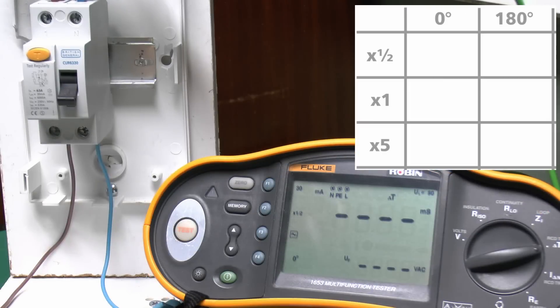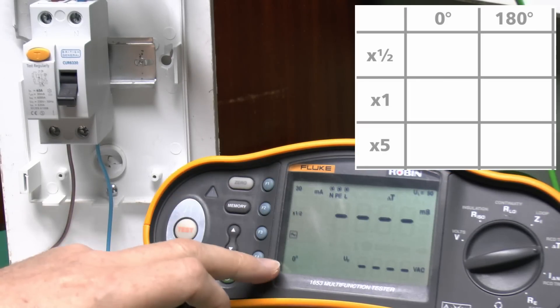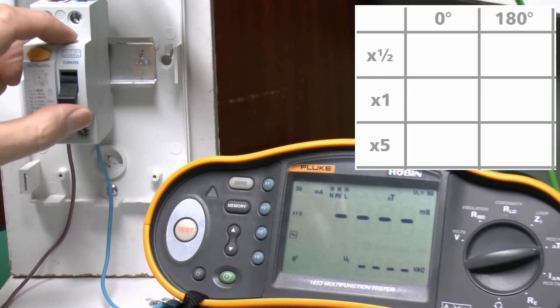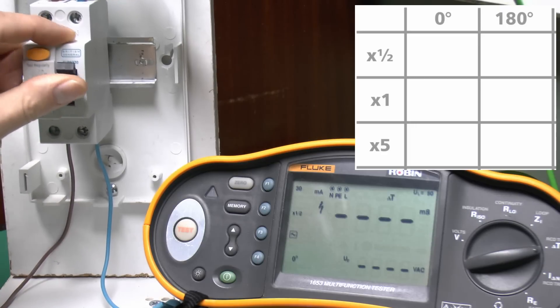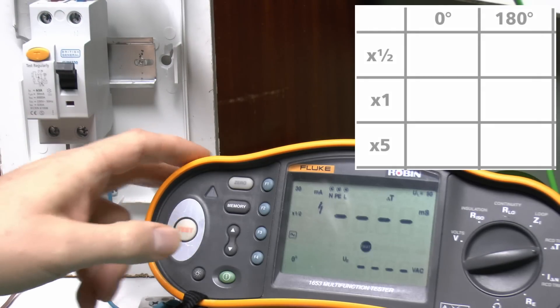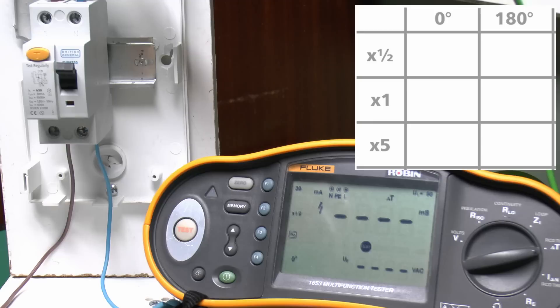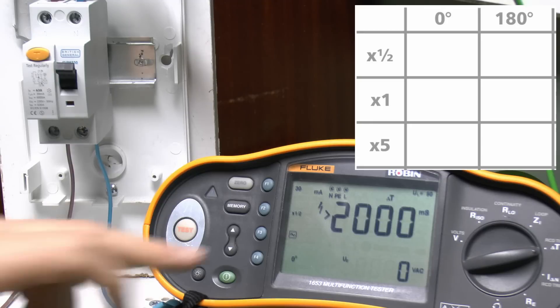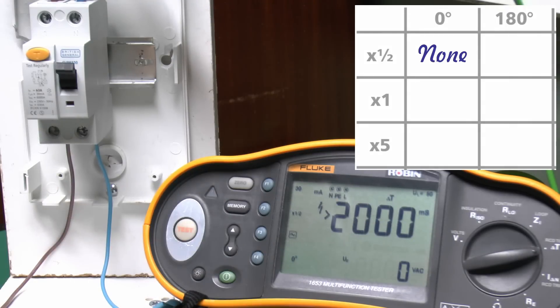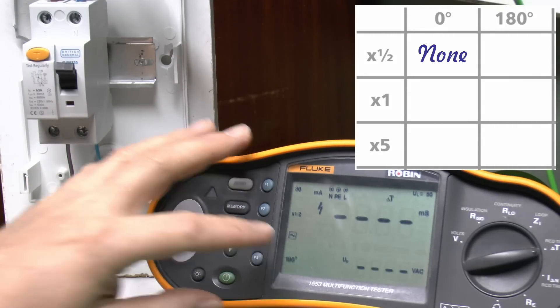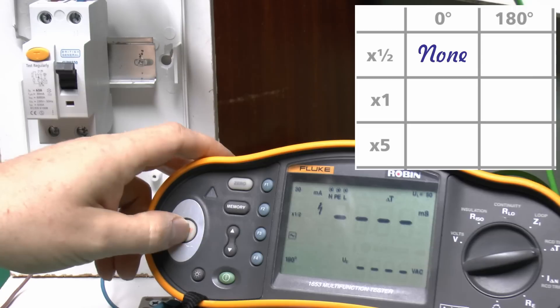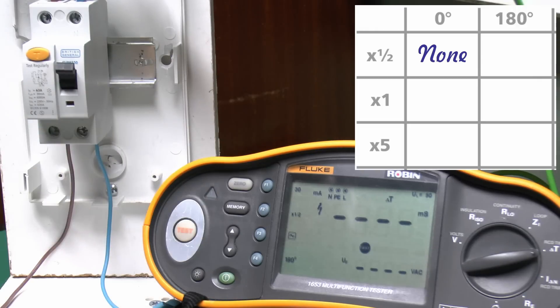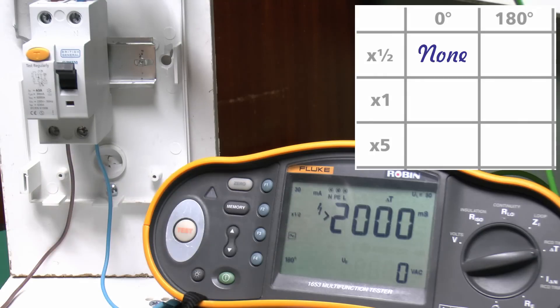So the first test, we'll use the half setting, and we'll do that at 0. So again, switch on. And this should not trip. And again, that doesn't trip, and we've simply got greater than 2,000 or 2 seconds. So again, that was successful, and we need to do it again on the 180 setting. So again, we'll test there, and that should not trip either, and once again, it did not.